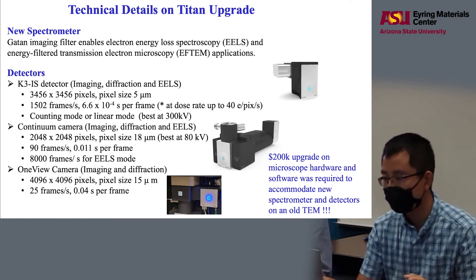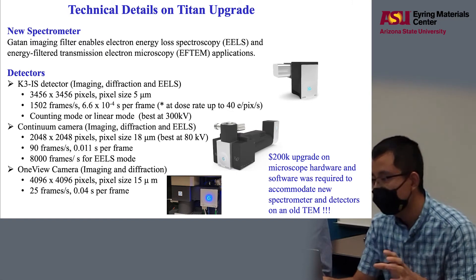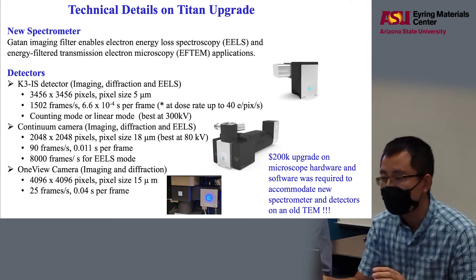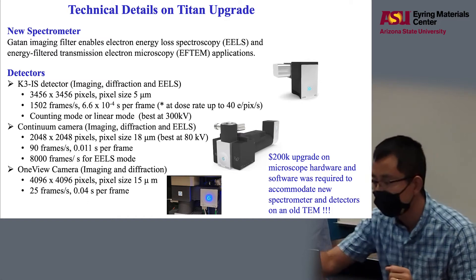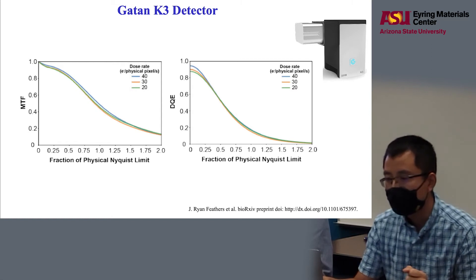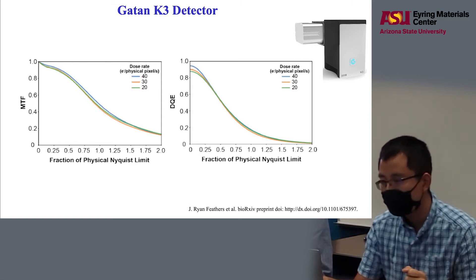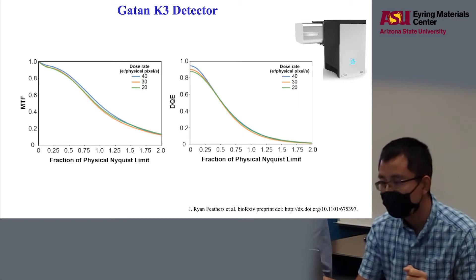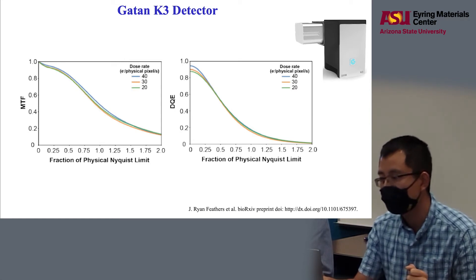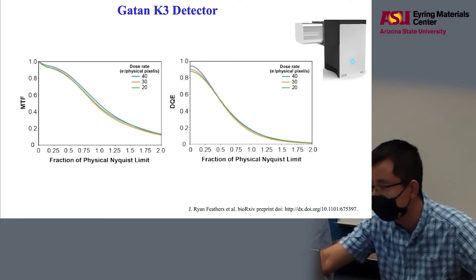Most users will be using the OneView camera. However, we needed to upgrade the microscope itself to allow the installation of these new instruments. Here is the K3 detector plot showing the modulation transfer function versus the Nyquist limit and also the DQE curve. They are very good at low frequencies, but can go down to 0.2 at one Nyquist limit.